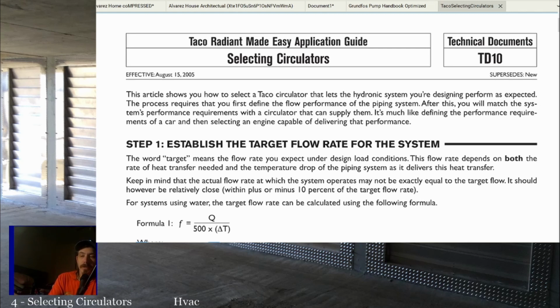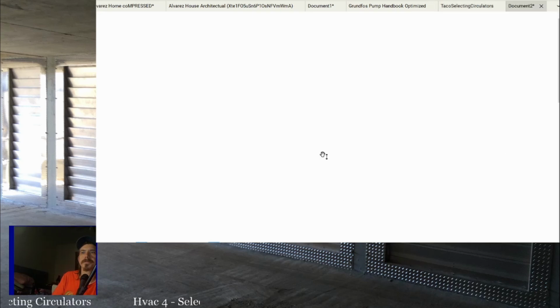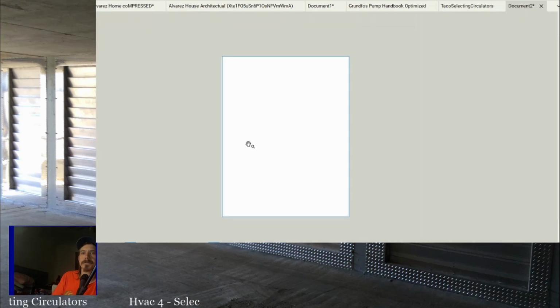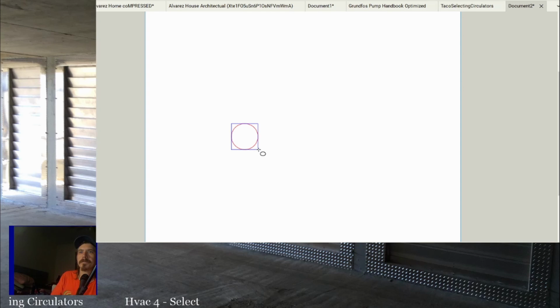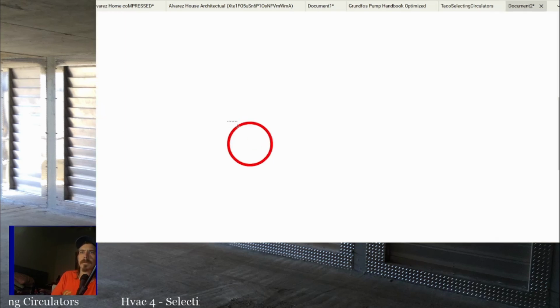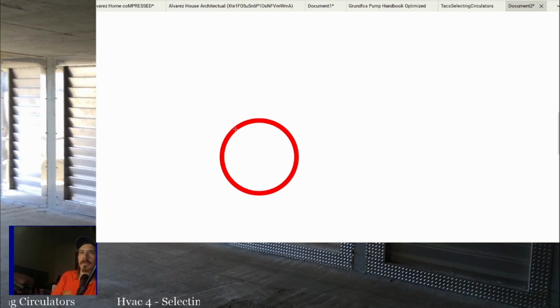All right. With a circulator, the suction side is coupled to the discharge side. So that means that the pressure, how high it has to pump, is canceled out by the fact that the suction side is pushing down on it that much too. So let me see. Can I make a quick picture? Is it worth it? I'll give it a shot real quick. All right. So in other words, if you've got a pump, right? See if I can draw something quick here.